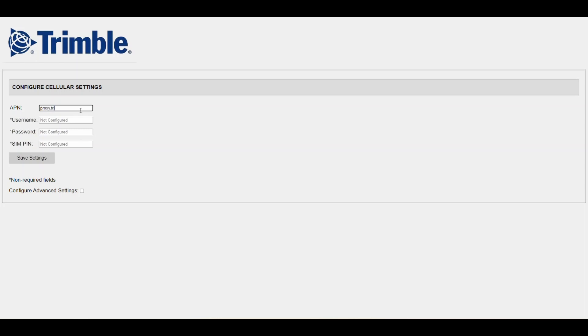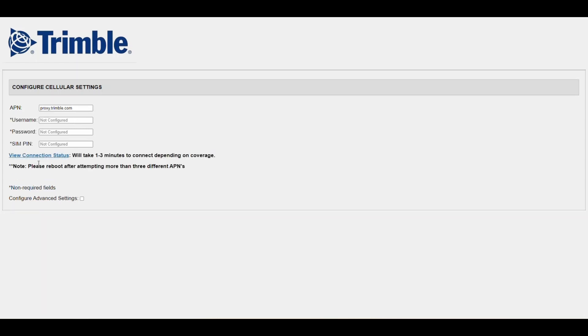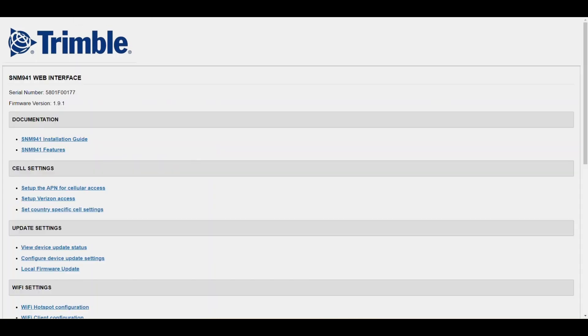The APN is carrier specific. The username and password fields are only required if the APN needs a username and password, and the SIM PIN field is only needed if the SIM card is set up to require a PIN. Otherwise, these can be left blank. With these two steps, both the APN and cellular provider mode will be configured for your SNM 941.